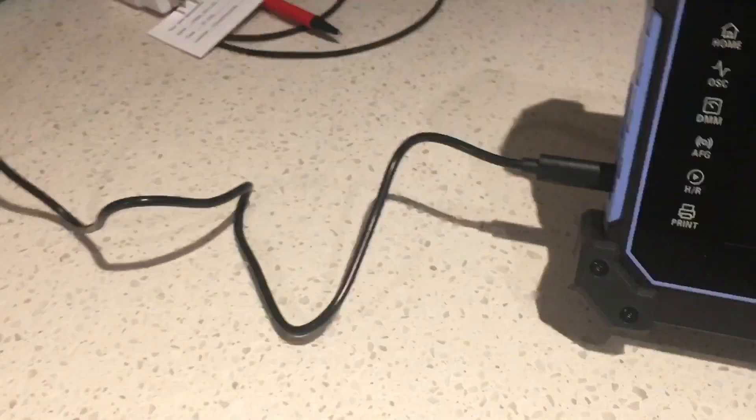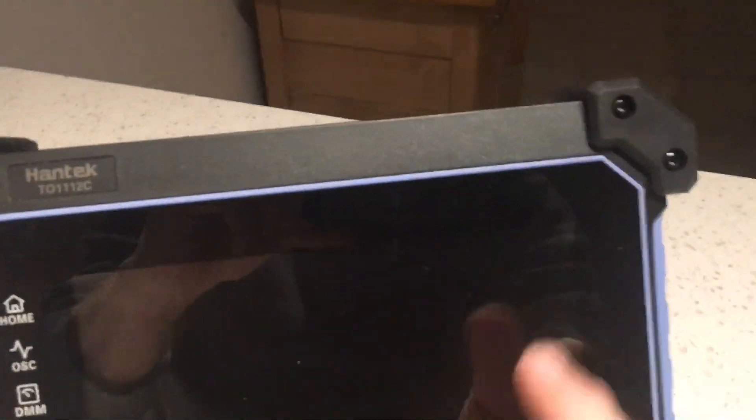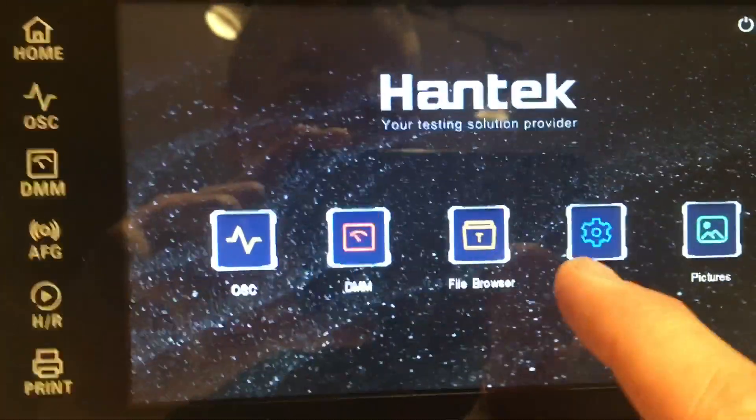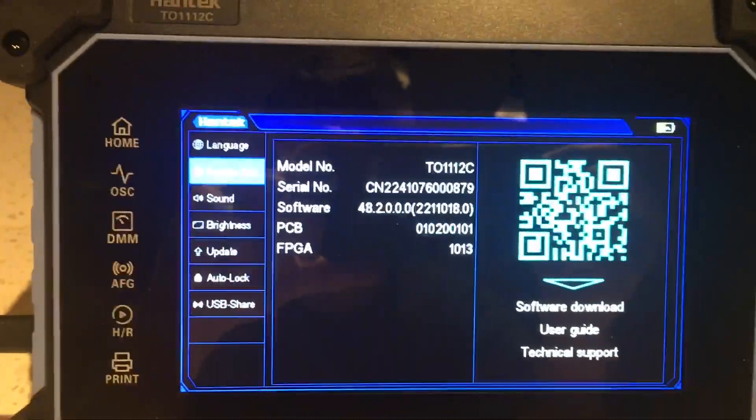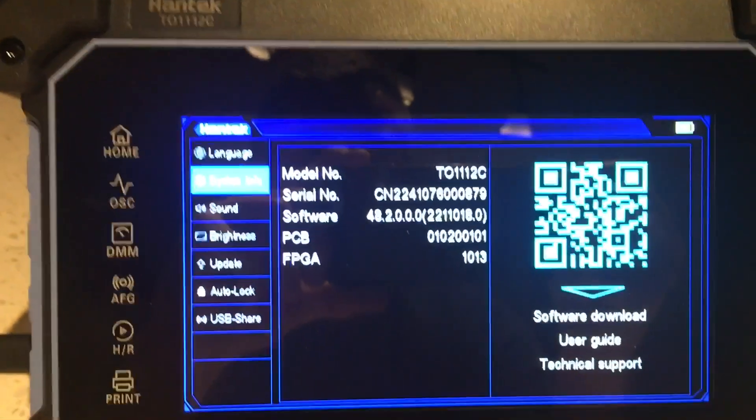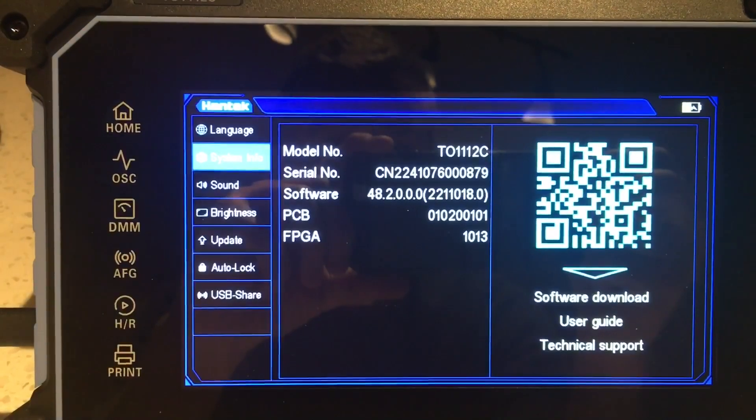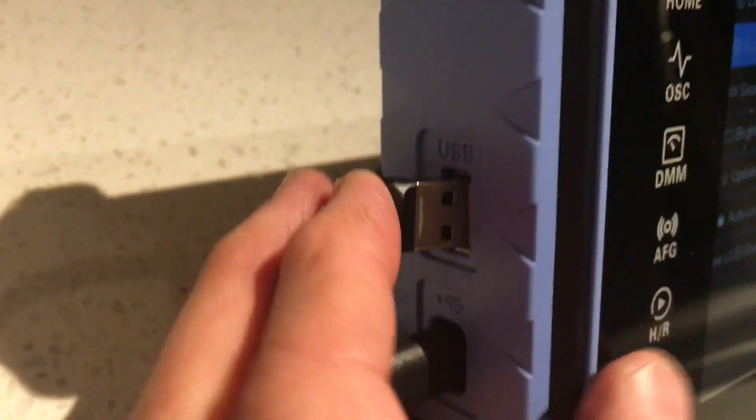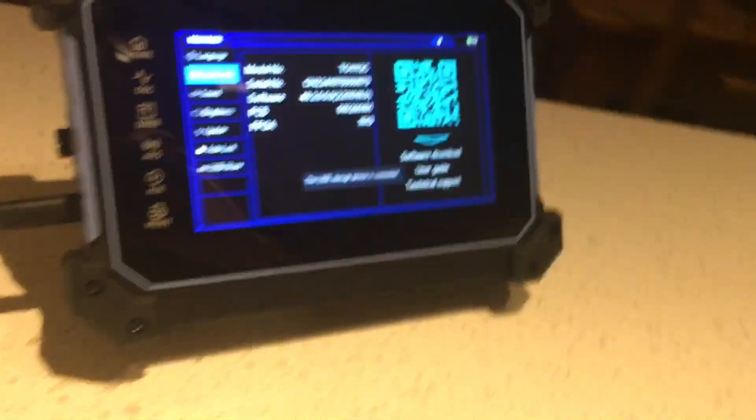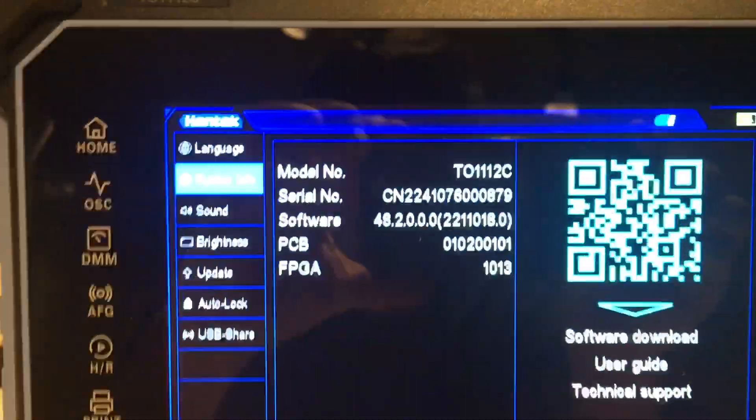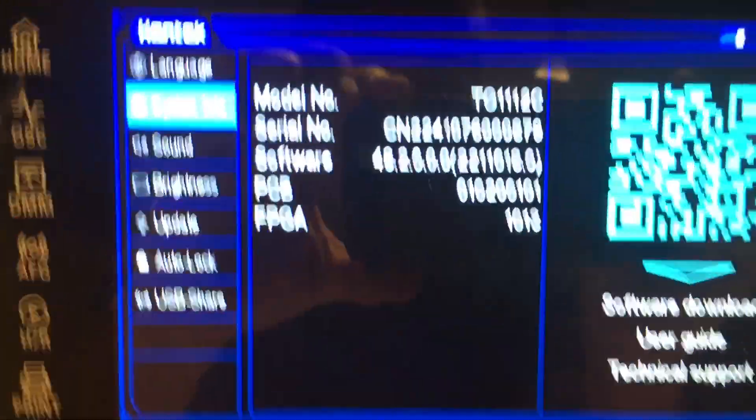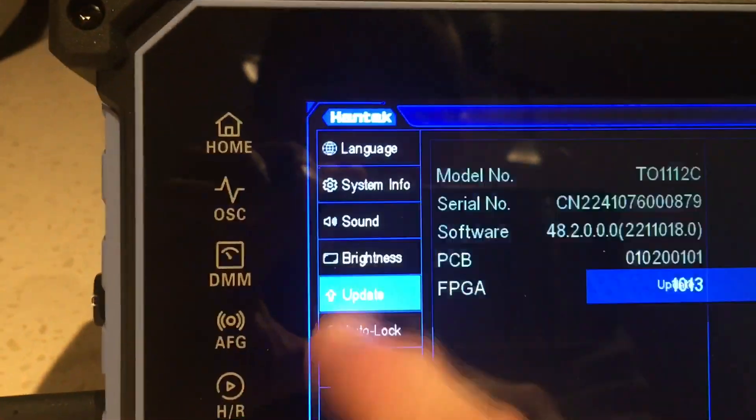So I highly recommend either being 100% certain about the capacity of your batteries or even better, just plug it in for the purposes of the update. The home page, settings. Here are the parameters. You'll notice nowhere on there does it say firmware. There is a software notation. So I'm inserting the USB. Yoko, can you keep it down a bit there? And go to update.